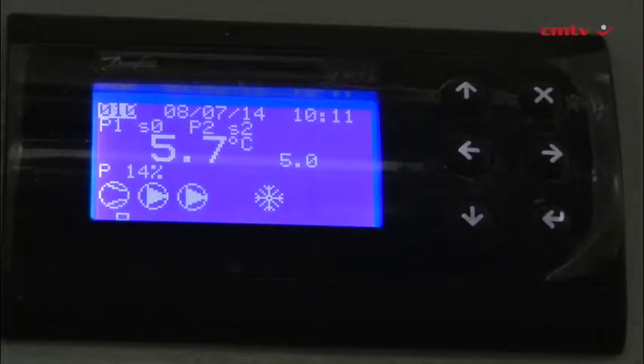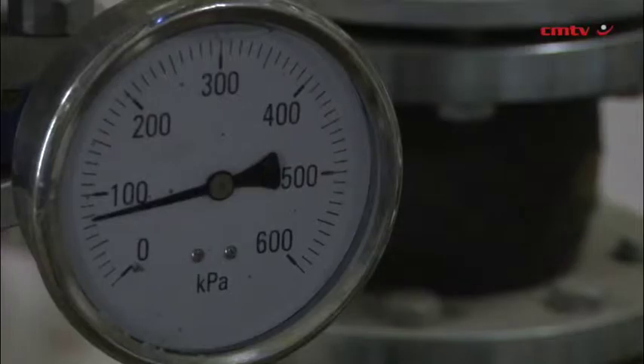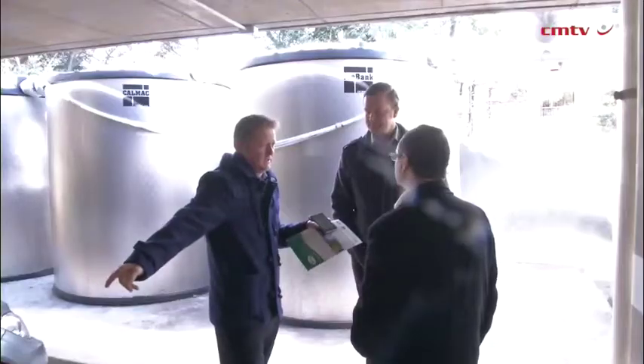of stored hot water. And explain to you in terms of the energy savings that you have as a result of the system. Well, essentially, we're giving them this hot water for free. So we're heating up that 54,000 litres for free. It's recovered heat whilst providing cooling to the hospital. So there is no cost to heat that, where previously you would pay to heat those 54,000 litres. And we are getting up to 55 degrees temperature hot water out of that in those tanks.